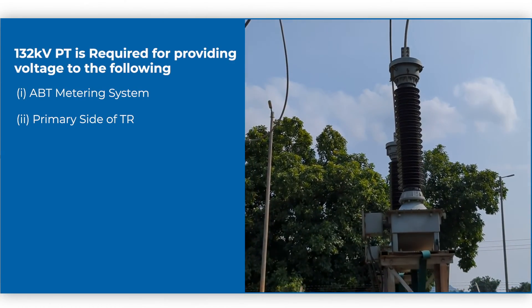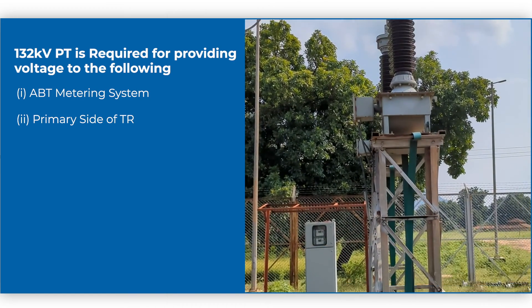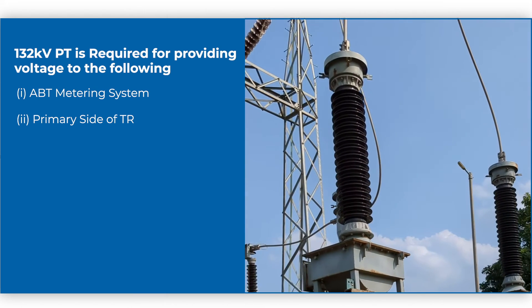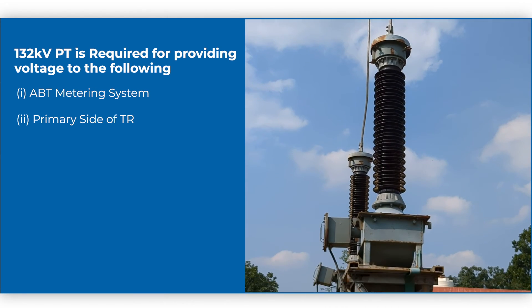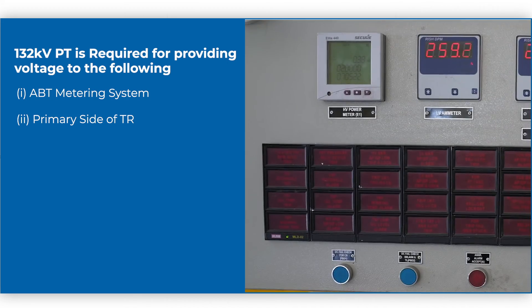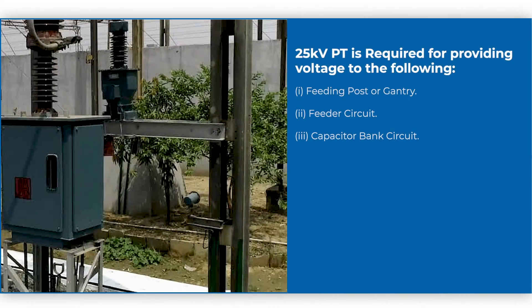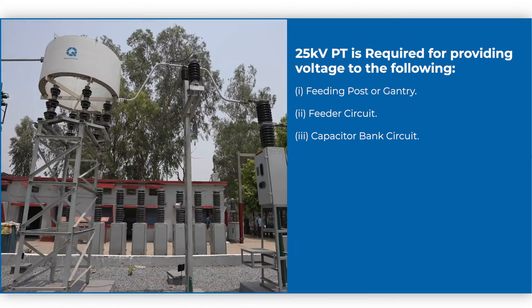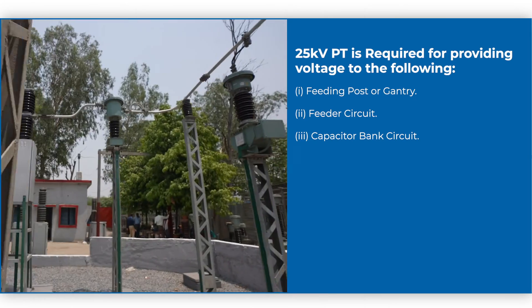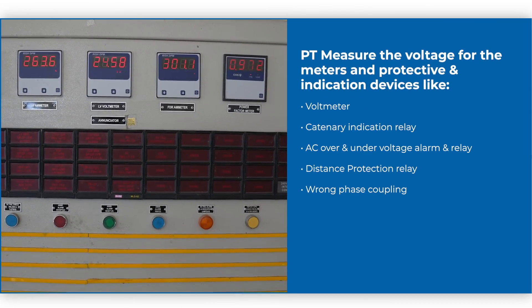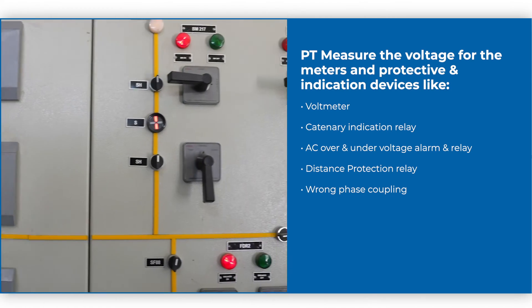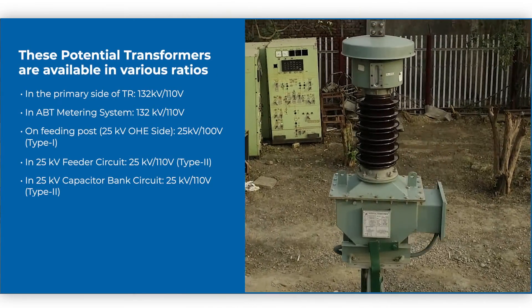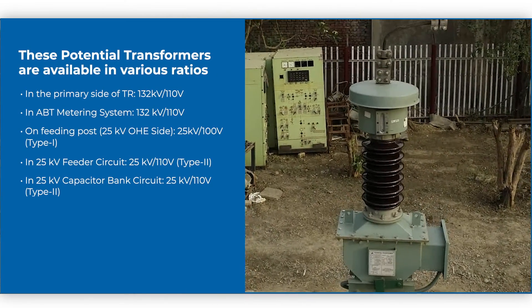Normally in TSS, 132 kV PTs are used only in the ABT metering system, but in some TSS, 132 kV PTs are provided between the CB and TR for voltage indication. 25 kV PT is provided on the gantry, feeder circuit, and capacitor bank circuit of the secondary side of single phase power transformer to sense or measure the voltage for meters, protective, and indication devices. These potential transformers are available in various ratios.